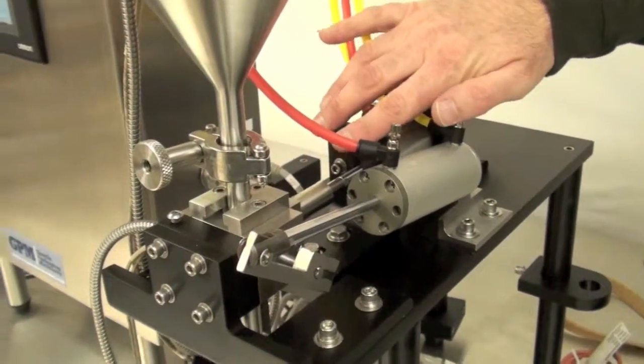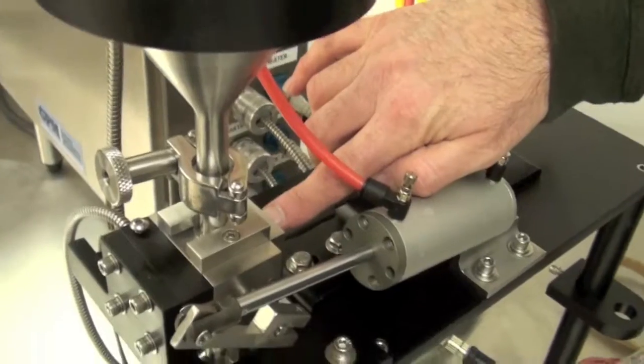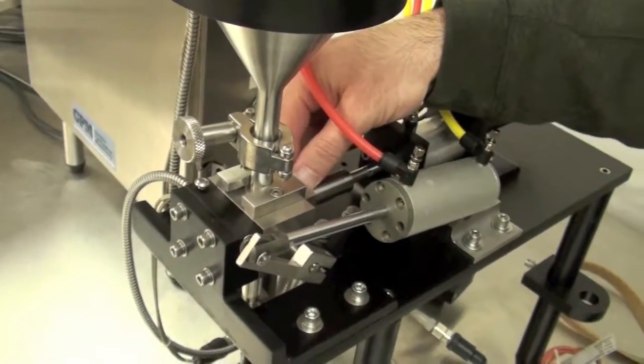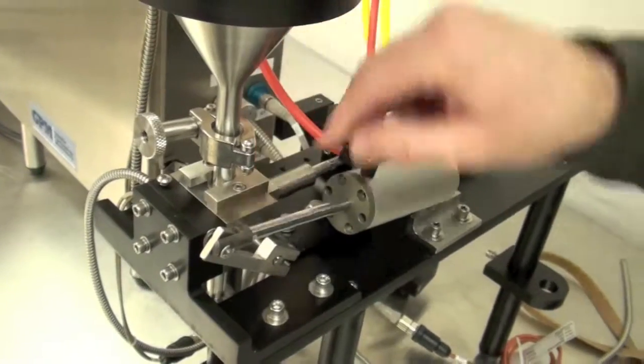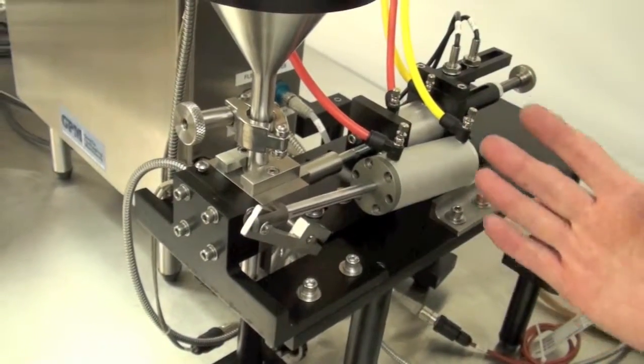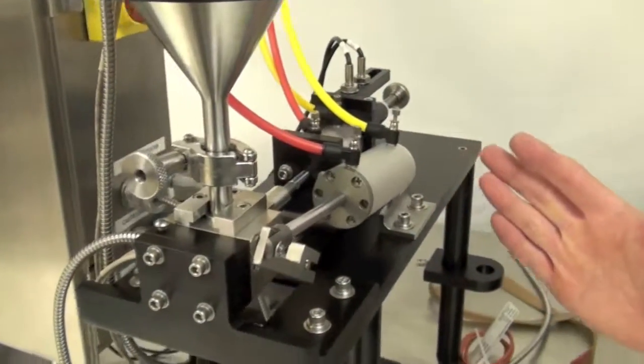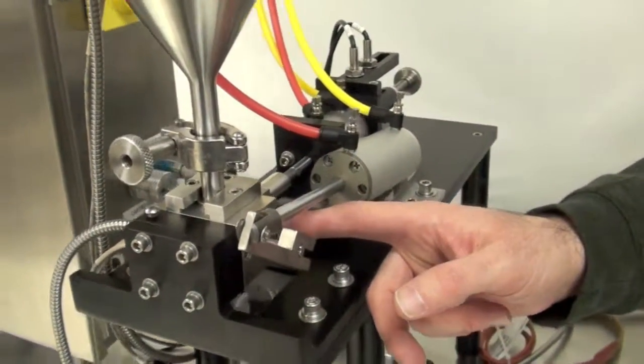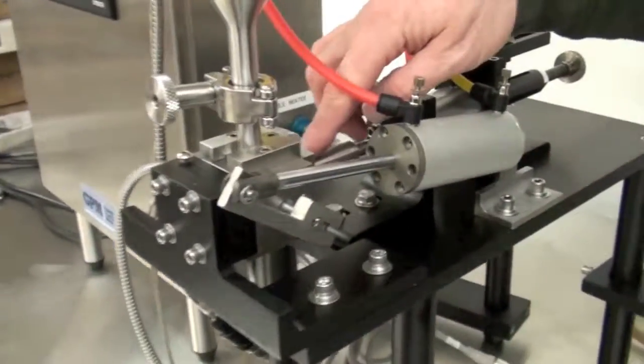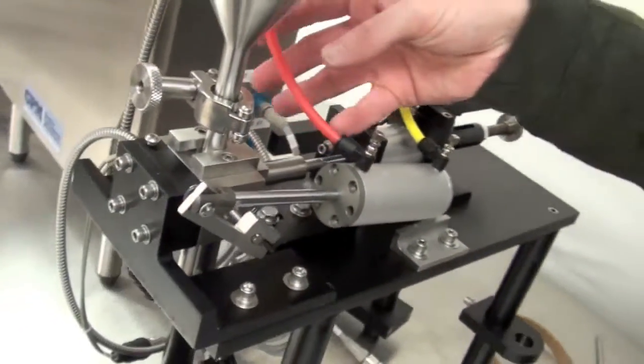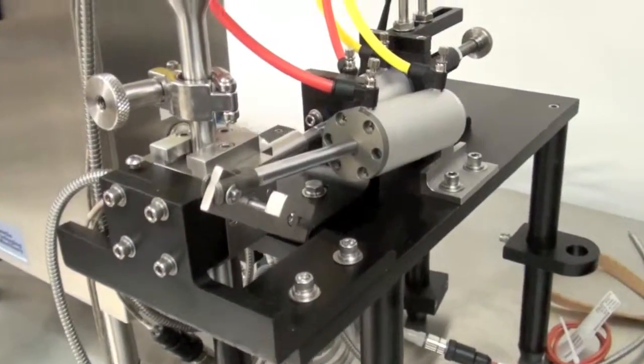So again, once the cylinder moves forward, there's the main piston dwell time that determines how long after it moves forward this will switch back. Now, the rotary piston return dwell time is how long after the valve closes before the main piston can return to pull new product for the next dose.